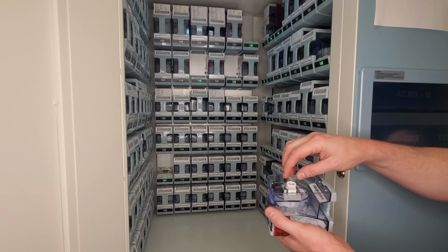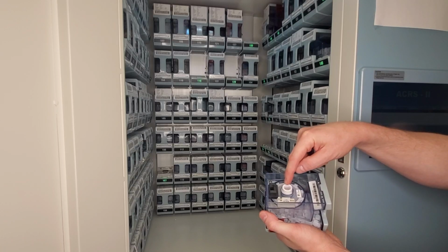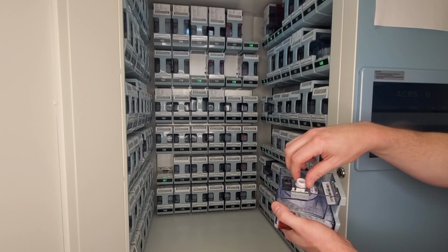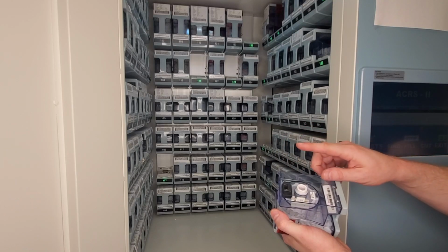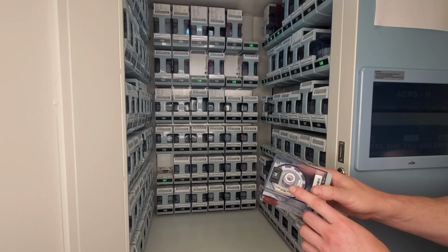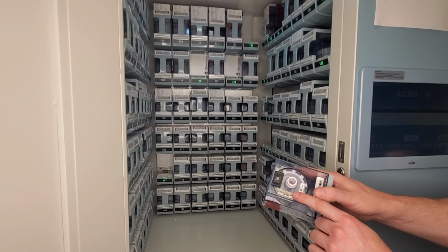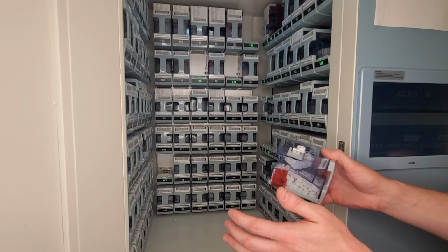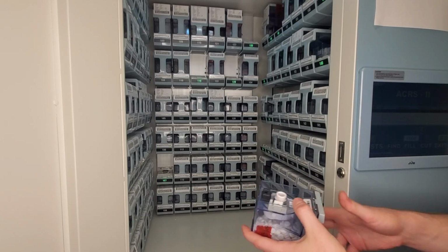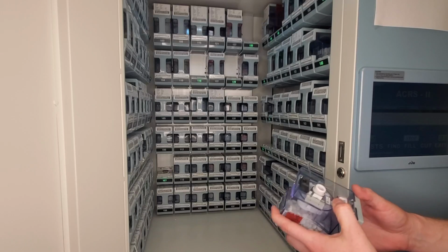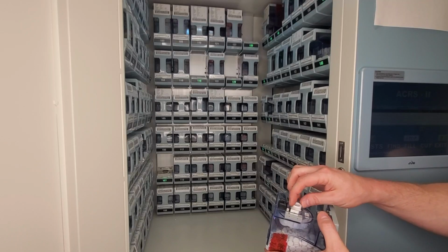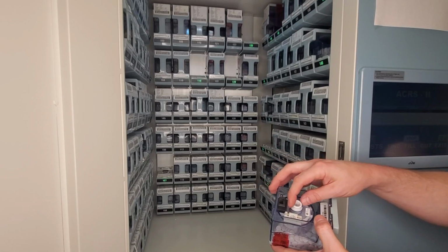I need to make sure that this white piece, known as the crown, can spin freely in each direction like this. If it cannot, I need to gently shake the canister, being very careful to not hit the microchip portion of the canister. I can shake it, I can hit it. The only thing I don't want to do is hit it up against the machine, the wall, or the floor, because the canister will break. Once I shake it and unjam it, it should spin freely like this.